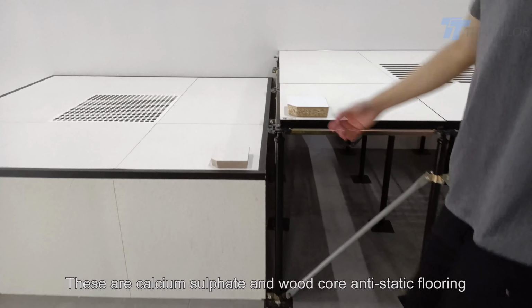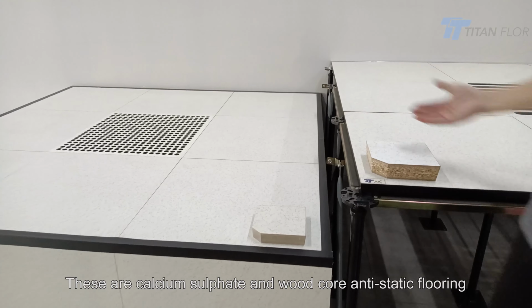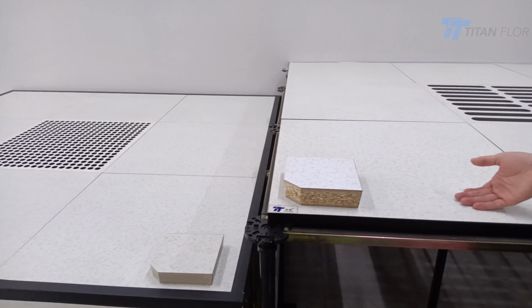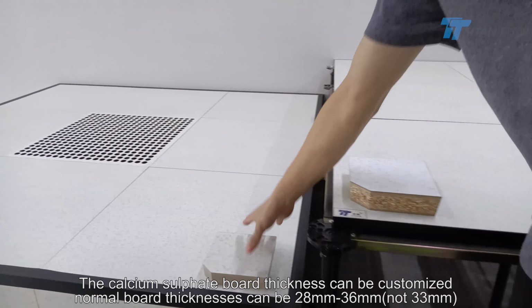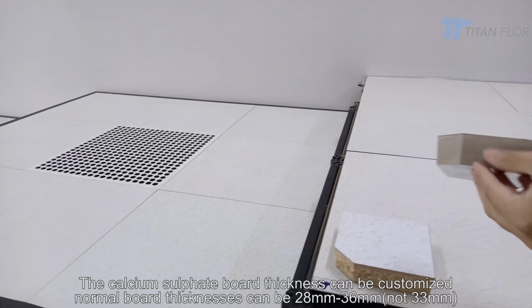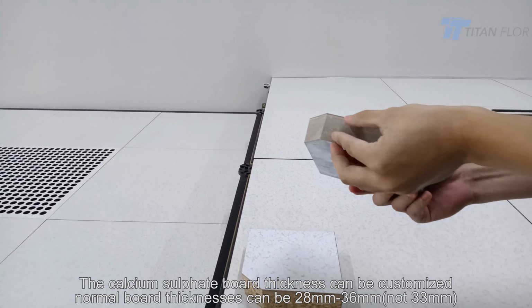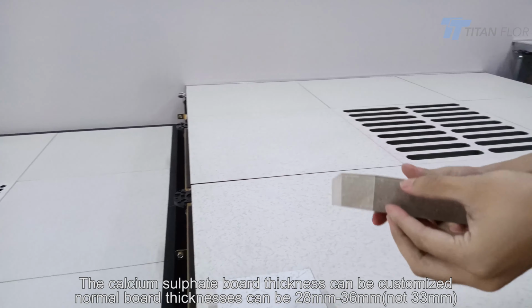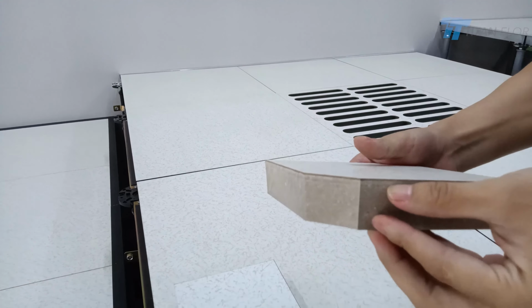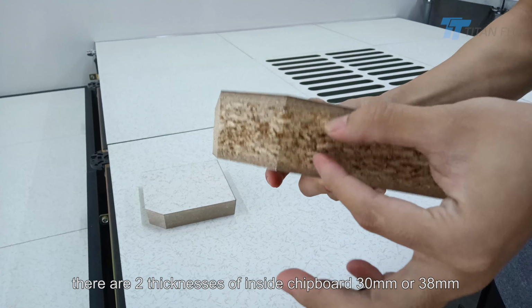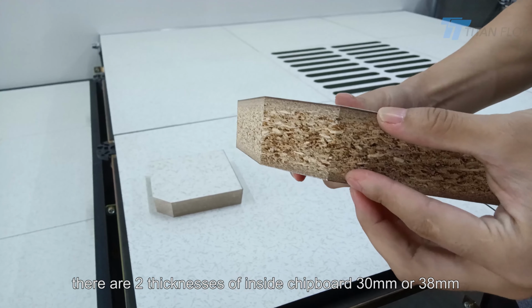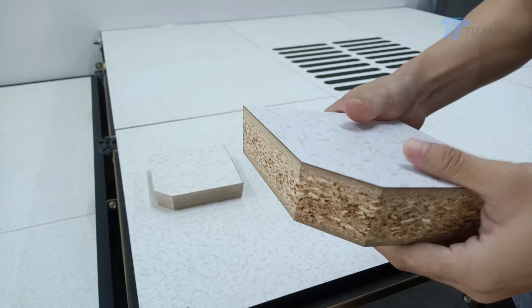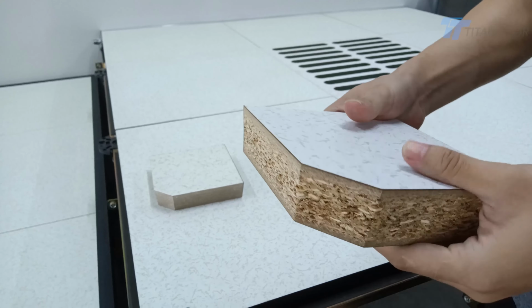These are calcium sulphate and wood core anti-static flooring. The calcium sulphate board thickness can be customized. Normal board thickness can be 28 to 36 mm. This one is a wood core flooring. There are two thicknesses of inside chipboard, 30 mm or 38 mm. The thicker the board, the higher the load capacity.